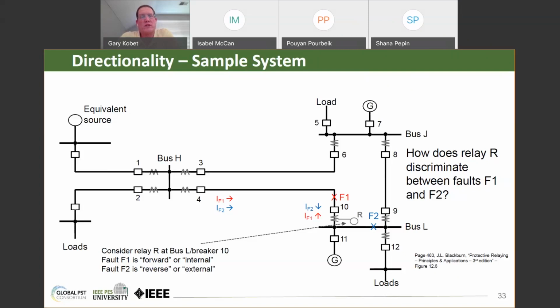For a bus fault, the voltage is going to go to 0, assuming a bolted fault. For fault F1, a fault just on the line side of the breaker, the voltage on the faulted phase or phases will be identical to a bus fault. The difference is the currents. For fault F1, the current flows from bus L to the fault up. For fault F2, the current flows down through breaker 10 to fault F2. And what the relay has to decide is: is the fault forward or reverse? So we have different polarizing methods that help the relay decide where the fault is. And so the issue here is discrimination.